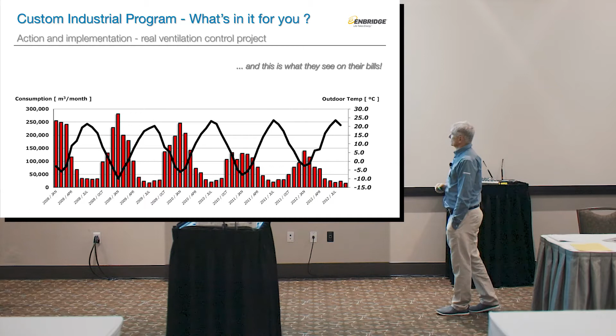$140,000 investment, all included, all audits. This is a unionized environment, so we had an air quality audit before and after. We had design, pre-design approval. We had design stage. We had install. All the hardware, $140,000 for about, they had 38 makeup air units and something like 120 exhaust fans that were all tied into this. So large system. This is not a small system.